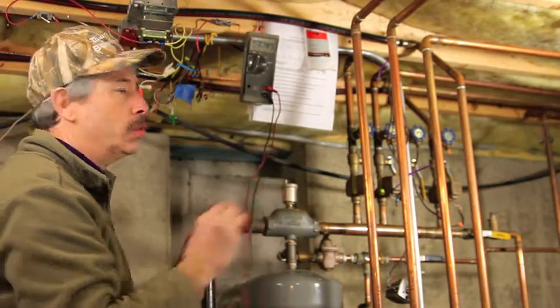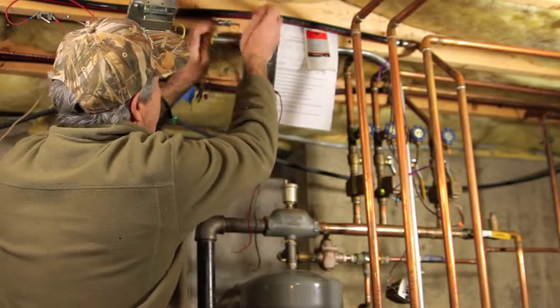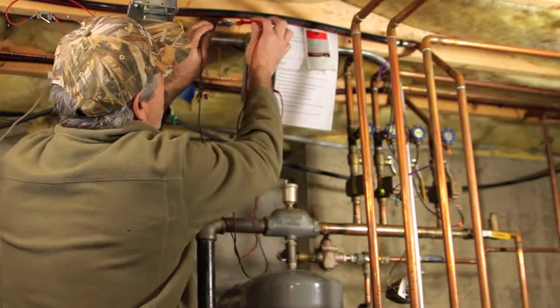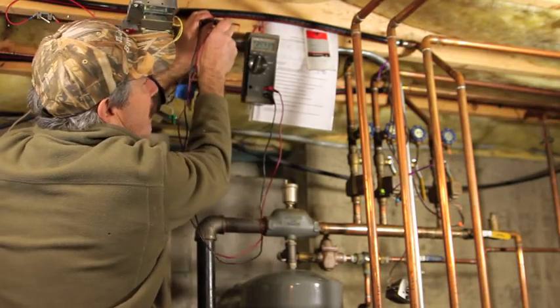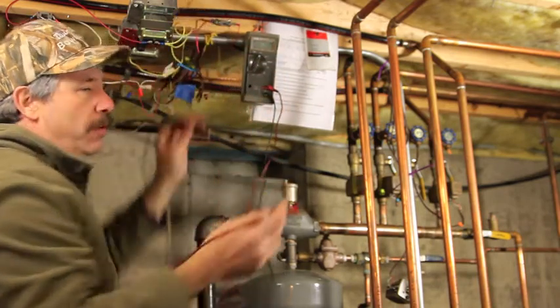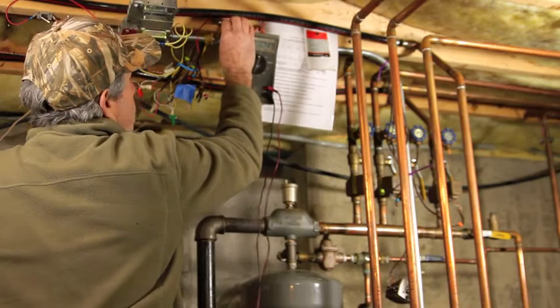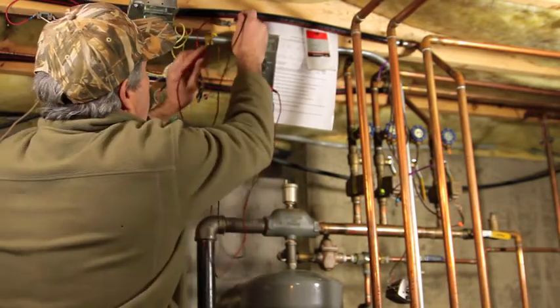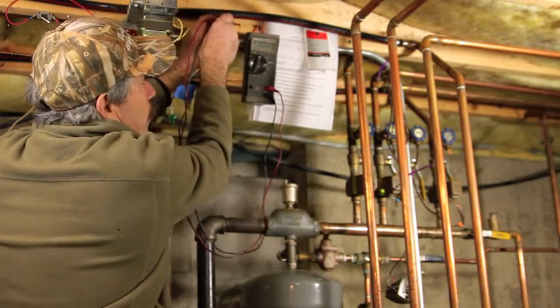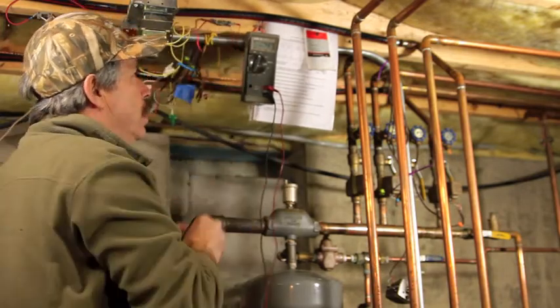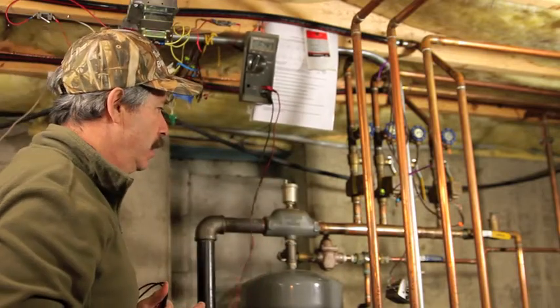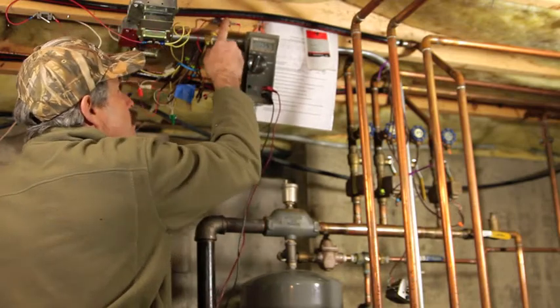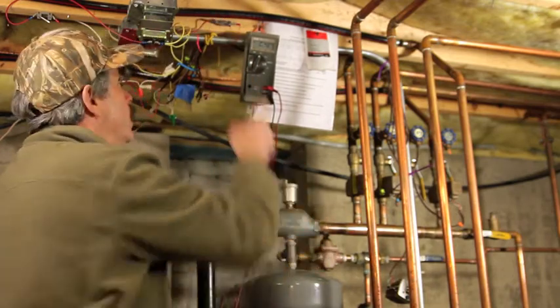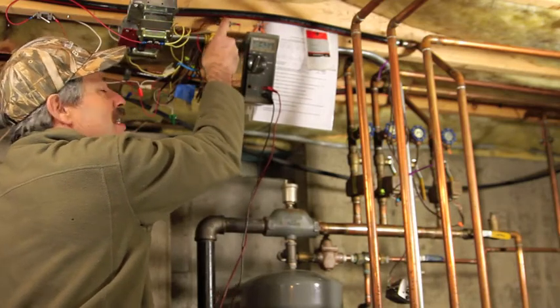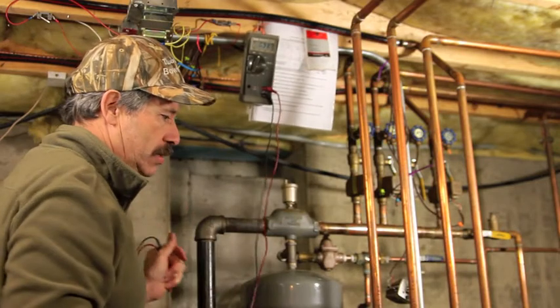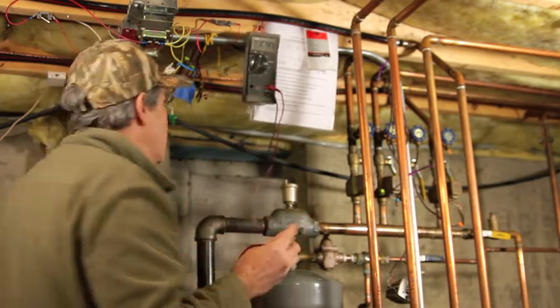Then when you come over to the fuse block and you measure both sides of the fuse, I'm pulling it out so it's an open. If you have an open fuse or a burned out fuse, you will get the full applied voltage of 24 to 26 volts. When the fuse makes that circuit, you will have just about nothing. You will have from 0 to 0.2, depending upon how much current's flowing through the system. If you want to know a little bit more, this is a resistor in effect. And if you have current flowing through it, you drop some of the voltage across the resistor, and you can use this as a current viewing resistor to measure the current in your system. But that's pretty simple, V equals I times R.